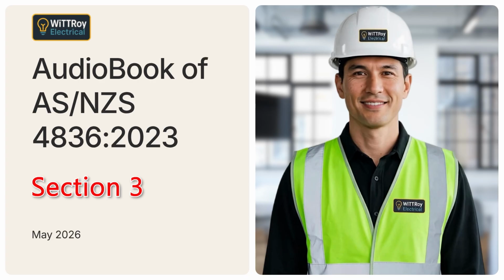A switchboard may be supplied by the normal mains supply, but it may also have solar, battery, generator, or UPS connections. A control circuit may appear small, but it may still create a dangerous backfeed. Control circuits or control systems must not be used as the means of isolation. A stop button is not isolation. An emergency stop is not isolation. A selector switch is not isolation. A programmable logic controller, or PLC, is not isolation.